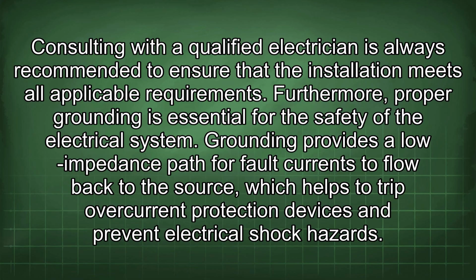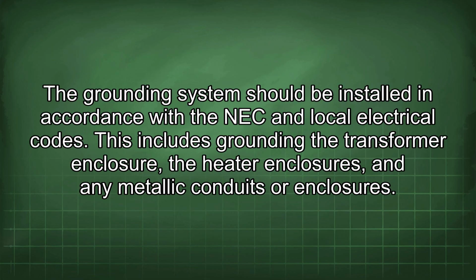Furthermore, proper grounding is essential for the safety of the electrical system. Grounding provides a low impedance path for fault currents to flow back to the source, which helps to trip overcurrent protection devices and prevent electrical shock hazards. The grounding system should be installed in accordance with the NEC and local electrical codes. This includes grounding the transformer enclosure, the heater enclosures, and any metallic conduits or enclosures.